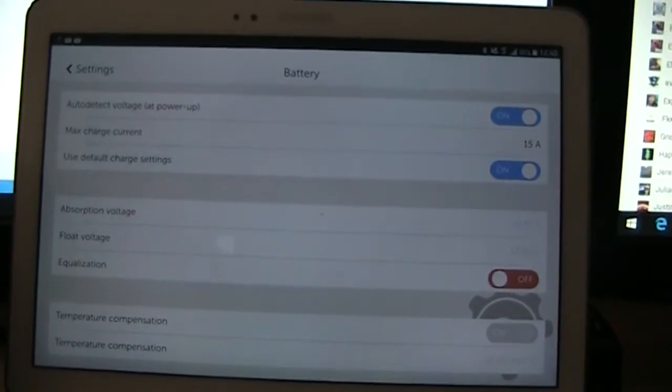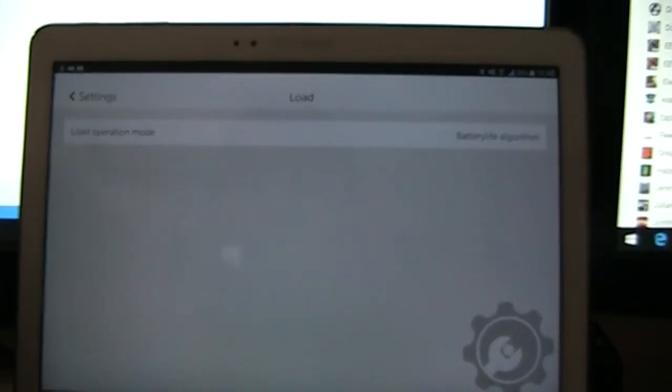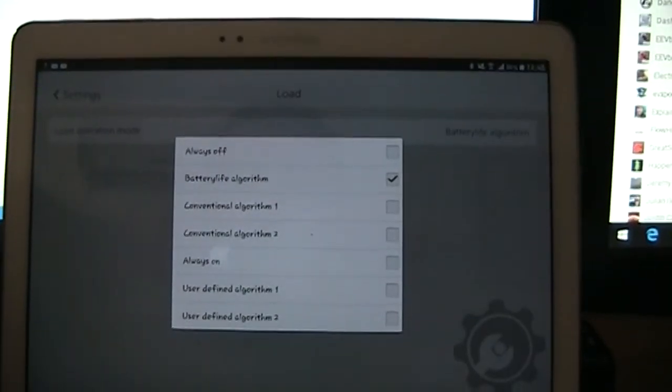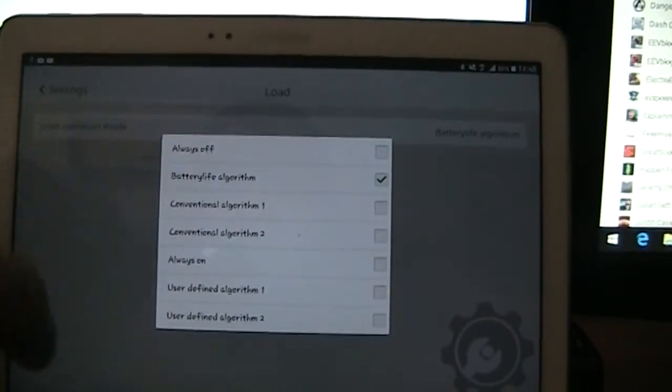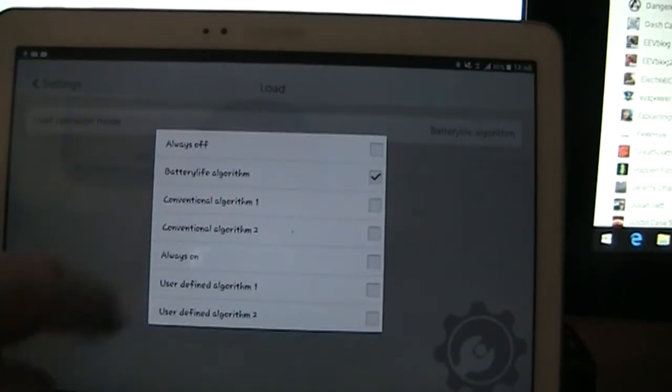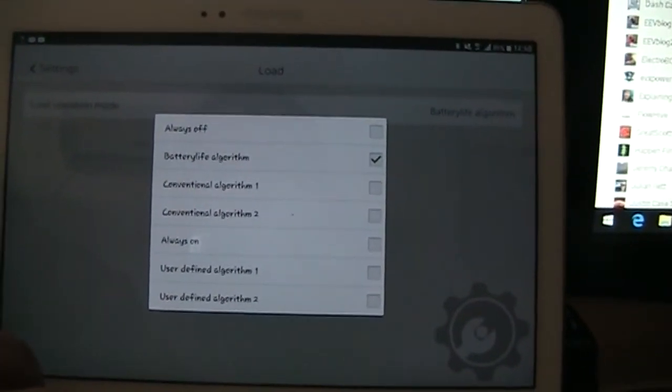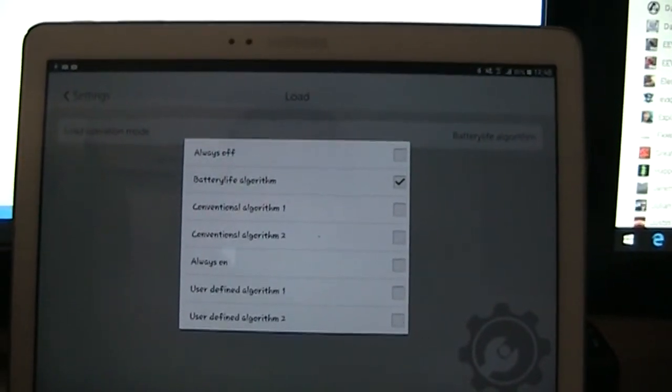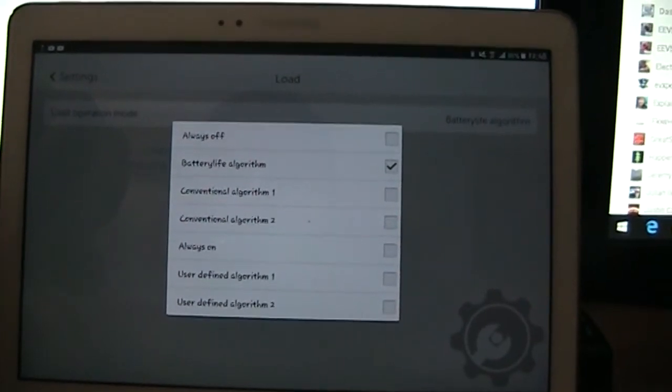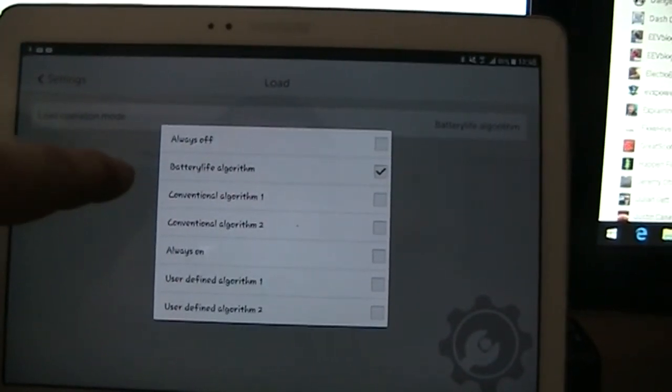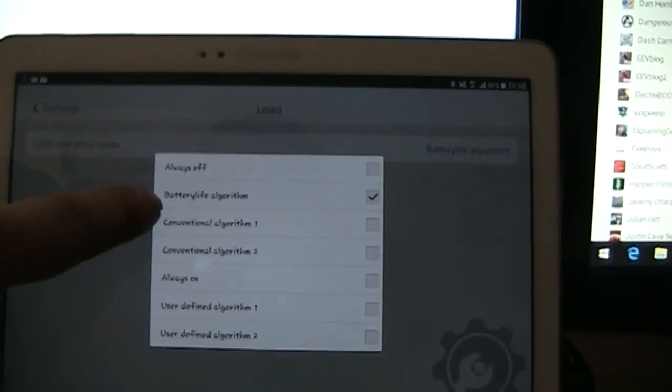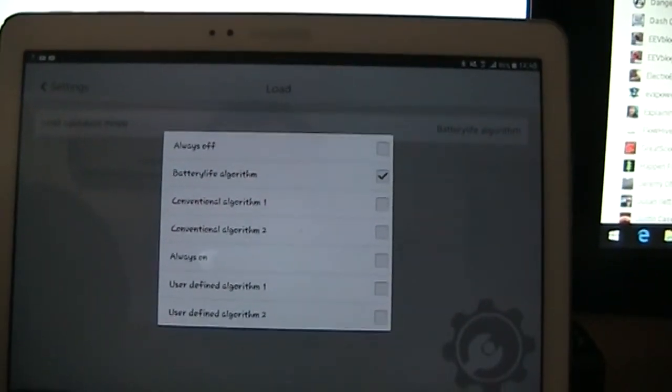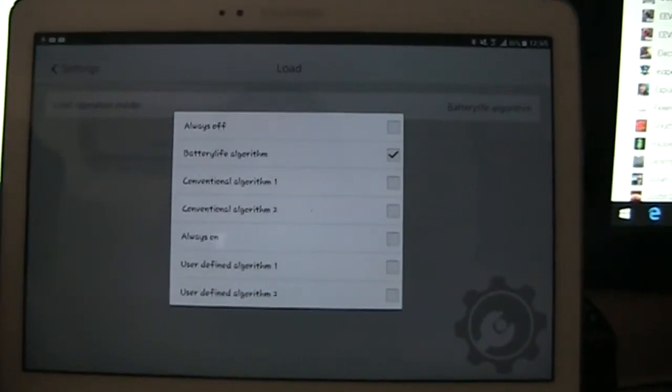So it's pretty handy. Let's go back. And on the load side of things, you can go to the different settings for the load. So it can be always off, conventional algorithms, always on, user defined. I haven't gone into that. Basically I just want the thing on all the time unless it goes under voltage. And I can't remember what that's set at, but I'd have to have a look in the manual. But at the moment it's set to this battery life algorithm so that if the battery voltage does go down too low, it'll turn the load off but automatically turn the load back on after the voltage recovers.